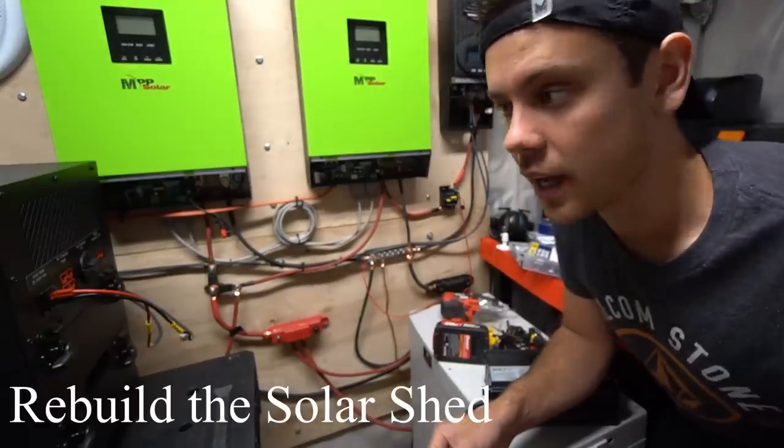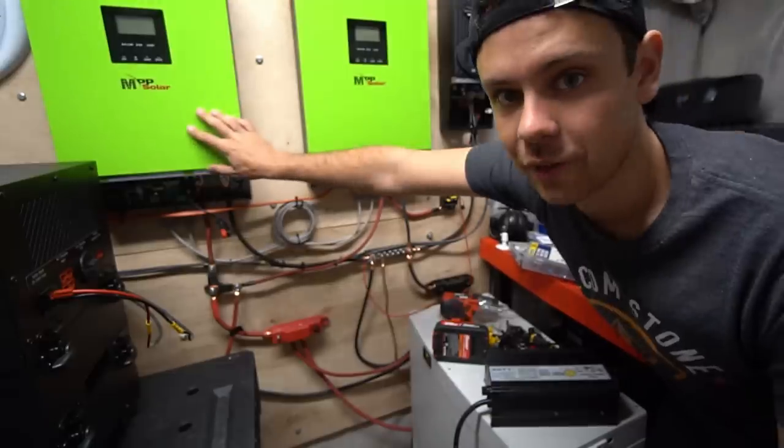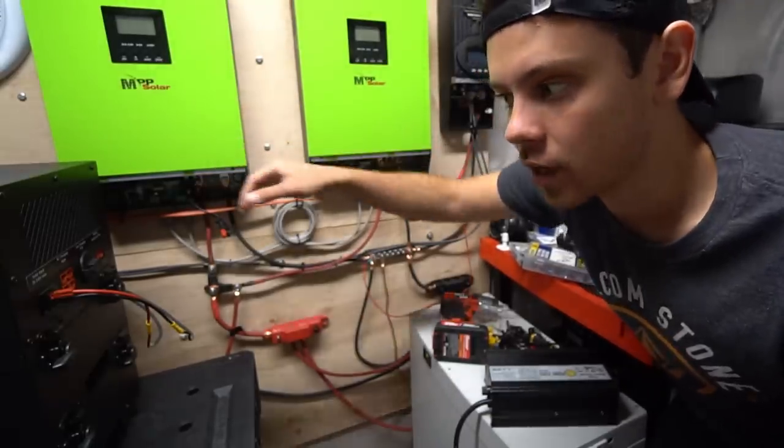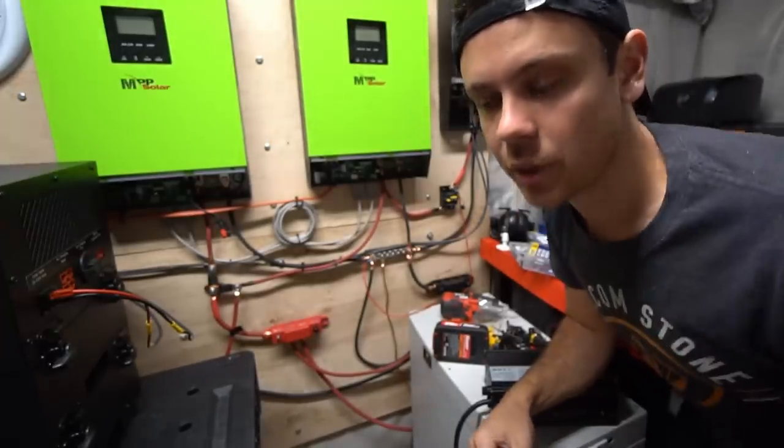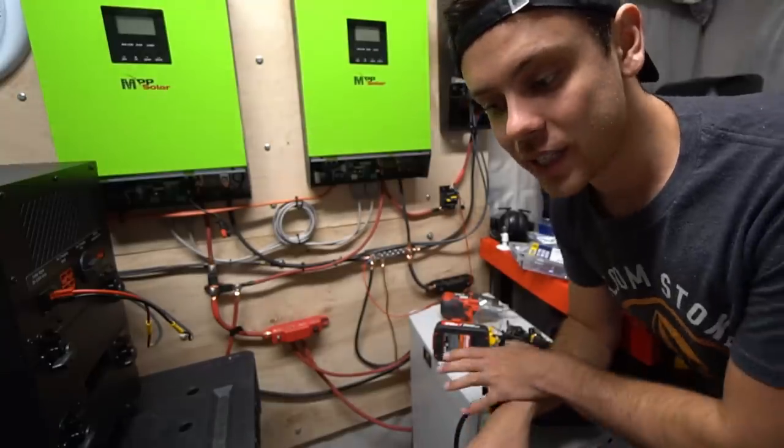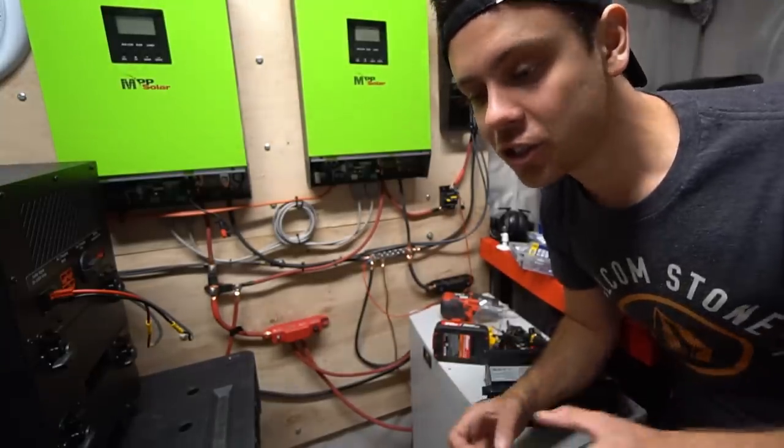Today we're going to rebuild the solar shed. So we have two LV2424s in parallel and they run at a nominal of 24 volts, but I want to run it at 48 volts with a smaller battery pack because currently it's 14 kilowatt hours and that's just too much.